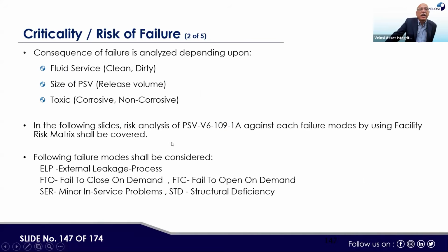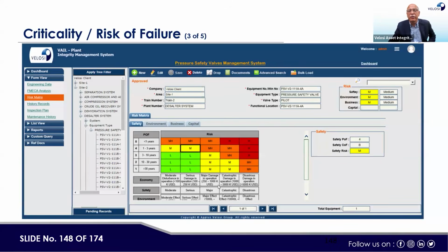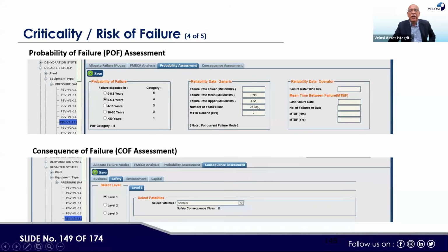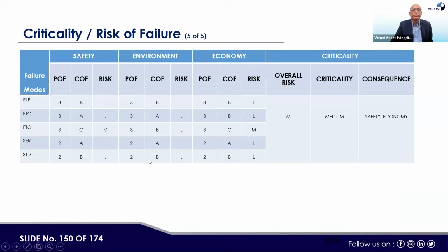So here, consequence of failure is analyzed: fluid service, clean, dirty, size of the PSV, toxic, whether the PSV is linked with the flare or not linked with the flare. Those aspects are also covered. Then the following failure modes, for example, external leakage process, fail to close on demand, in-service problem, are all covered. This is the risk position of that particular PSV, whether medium or high risk. Then accordingly, the probability is taken based on the reliability data, MTBF based, and this is the consequence of failure, which is level 1 or level 2, right? Then criticality, risk failures: for all failure modes we have assigned POF, COF, risk. This is safety, environment, economy, criticality, medium for this particular one. The leading one is taken here.